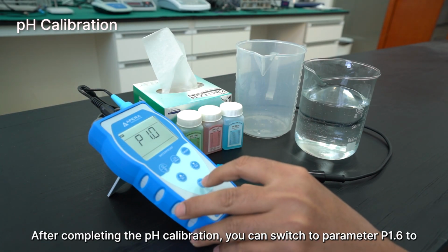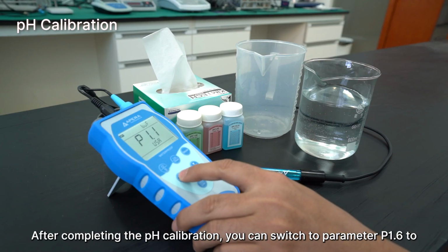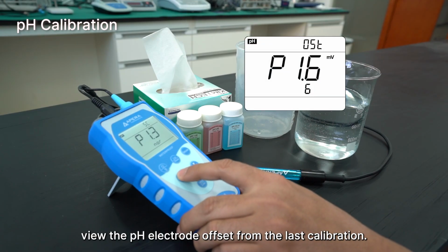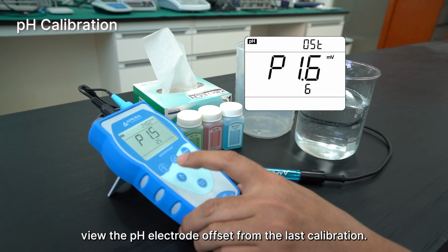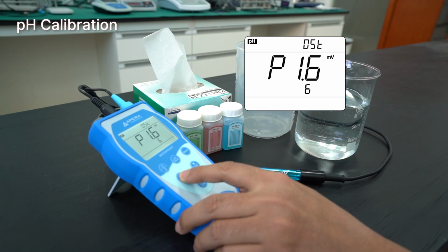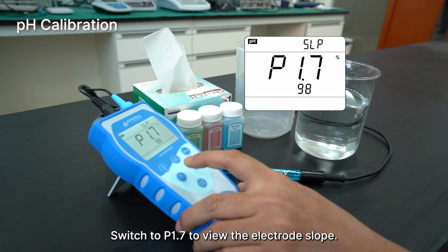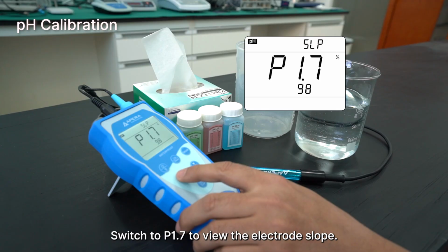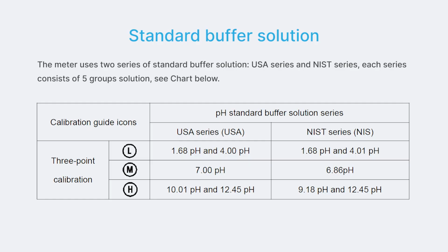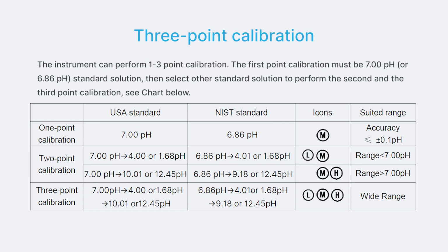After completing the pH calibration, you can switch to parameter P1.6 to view the pH electrode offset from the last calibration. Switch to P1.7 to view the electrode slope. The meter supports 2 buffer sets, USA and NIST, each with 5 solutions. The meter supports 1 to 3-point calibration, starting with 7.00 pH or 6.86 pH, as shown below.